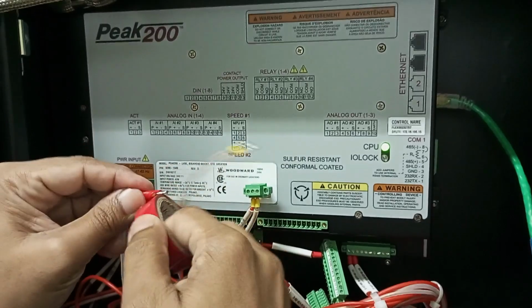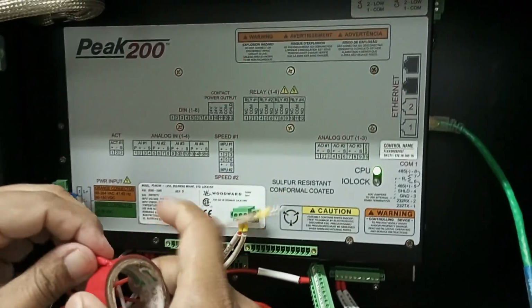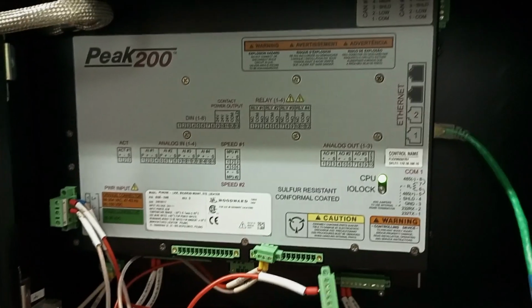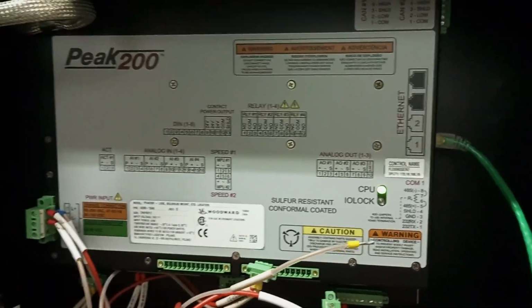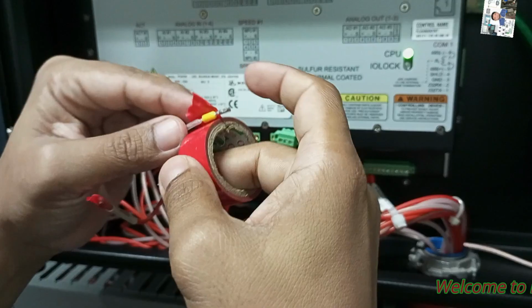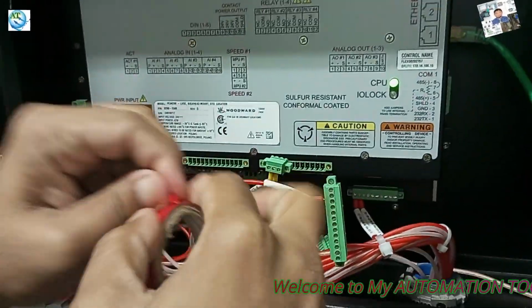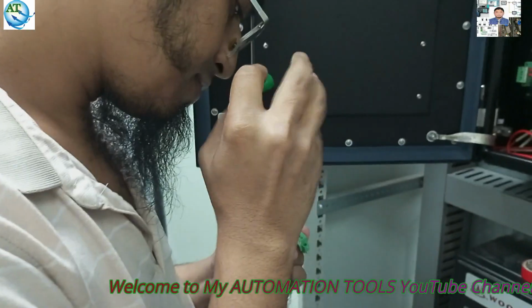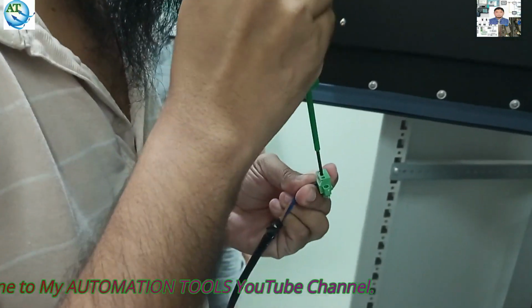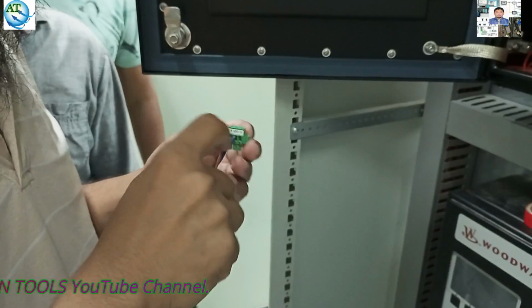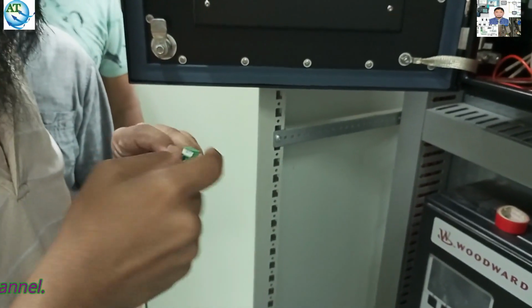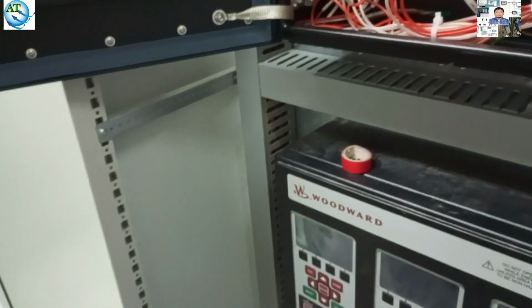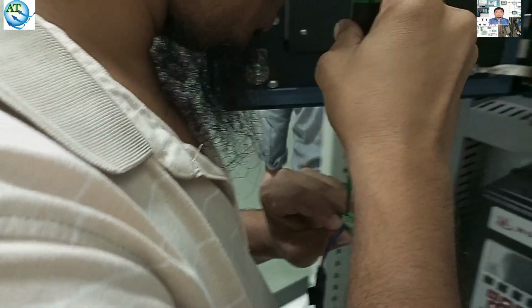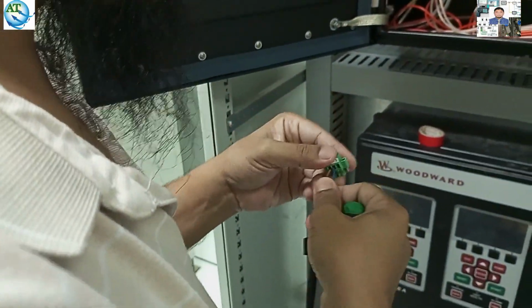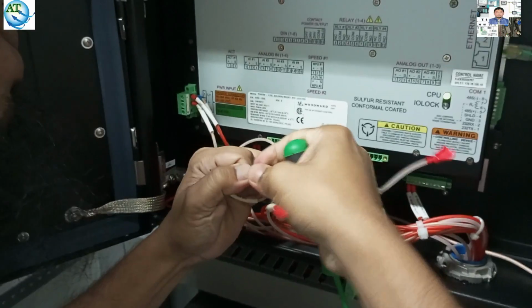For that, we have to supply two speed inputs. You see, the Peak 200 controller takes two speed inputs and one actuator output. By using this Woodward Speed Loop Tester, we can supply speed and also get the actuator output. So we are preparing cables for connecting this controller with the Woodward Speed Loop Tester. We need two cables for the two speed inputs and one cable for the actuator output.